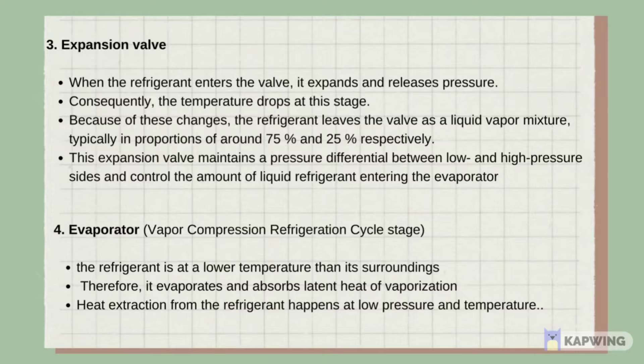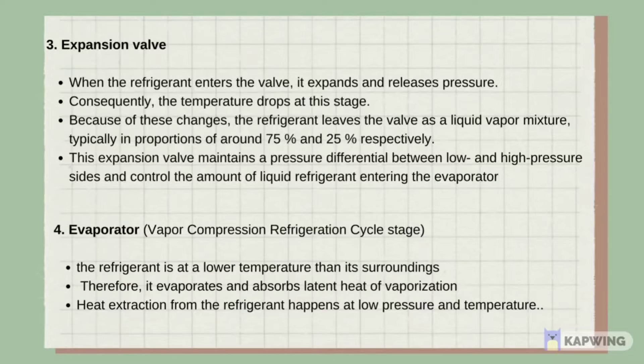The expansion valve maintains a pressure differential between the low and high pressure sides and controls the amount of liquid refrigerant entering the evaporator. The last component is the evaporator, which is the final stage of the vapor compression refrigeration cycle. At this stage the refrigerant is at a lower temperature than its surroundings, so it evaporates and absorbs latent heat of vaporization. Heat extraction from the refrigerant happens at low pressure and low temperature.